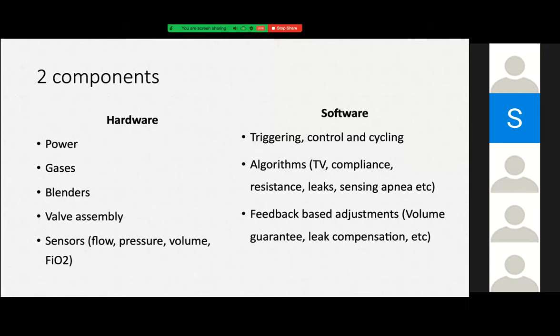The software part, which I will not be dealing with in this presentation, includes mechanisms for triggering, controlling, and cycling. It also includes algorithms which measure tidal volume, compliance, resistance, leaks, and which sense apnea. We also have feedback-based adjustments like volume guarantee modes and leak compensations. Today's presentation is primarily based on the hardware of the ventilator.